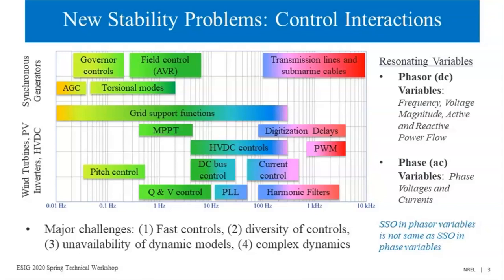We also need to understand that when we talk about oscillations, we have to differentiate between whether we are talking about oscillations in phasor variables like active and reactive power flow, frequency and voltage magnitude, or phase variables. Subsynchronous oscillations in active and reactive power, like in torsional oscillations, are very different from subsynchronous oscillations in phase voltages and currents, which we see in SSR and type 3 wind problems, and both require different kinds of models. I just wanted to highlight this because at certain times we miss this differentiation between the two sets of problems.